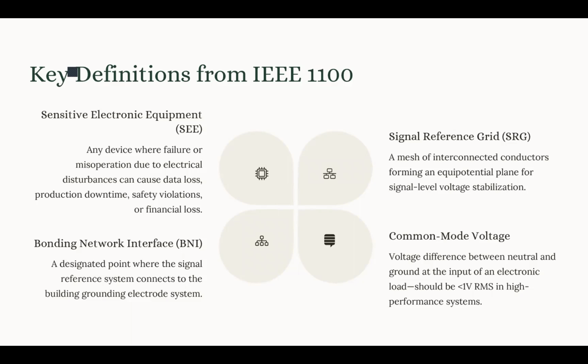The last definition that we want to mention is the bonding network interface, which is a designated connection point where the signal reference system, that SRG that we talked about, interfaces with the building's grounding electrode systems. It is important to prevent floating ground potentials and control circulating current by providing a single low impedance bonding point. The recommendation in this standard is to use solid, corrosion resistant bonding and a low impedance connection to make sure the high frequency transients are diverted safely to the building ground.